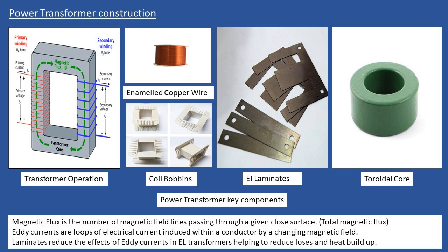And you can see the different constructions. With an EI, it's laminated steel. If you think about the toroidal, or maybe the donut that you see here, then that's nickel iron. And then with the R-core, it's high-end silicon steel strips, but it's continuous. And that's what helps then to reduce that overall effect that we see there.